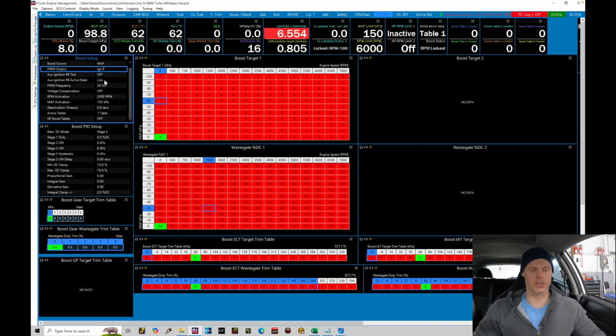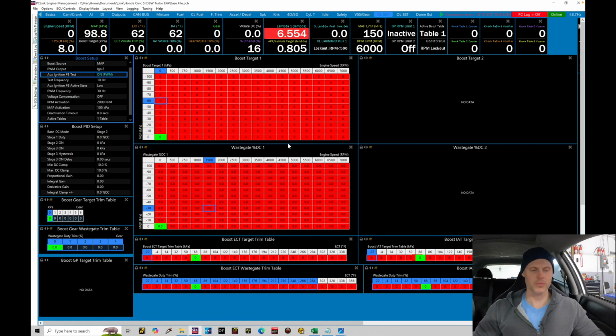Right now we can test this. We want to make sure the state is low, setting a low side pulse since I've powered the solenoid with one wire. The other wire is what we're pulse width modulating on the low. If I turn on pulse width modulate and set the test frequency to something like 30 hertz, I can hear the solenoid buzzing. You probably can't pick it up in the audio, but it's functioning, so we know it's all good to go here, and we'll click off.